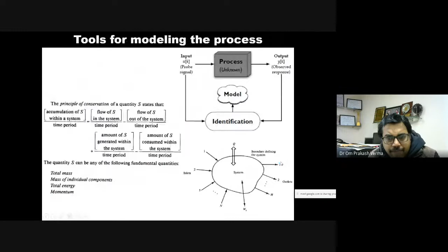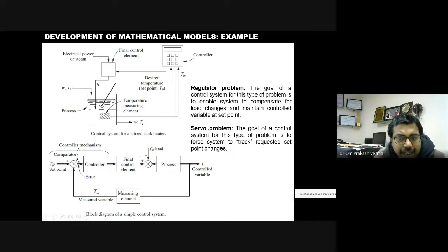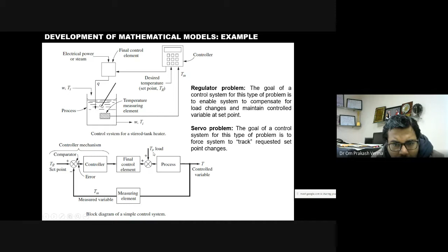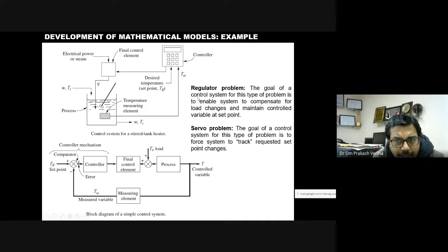So what does the regulator problem mean? The goal of the control system for this type of problem is to enable the system to compensate for the load change and maintain the controlled variable at the set point. It means for the regulator problem, the set point is going to be constant. The variation is only happening in the TI load. Okay, the set point will not change, however the load will change in the case of the regulator problem, and the vice versa happens in the servo problem. The servo problem is used for tracking purposes. Tracking means the set point will change, however the load will become constant. Load will not change in the servo problem. Okay, so generally robotics problems are encountered with the servo problem, however most chemical problems are encountered with the regulator problem. Right.